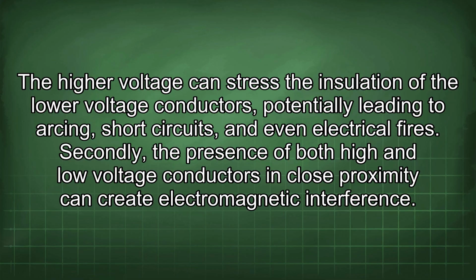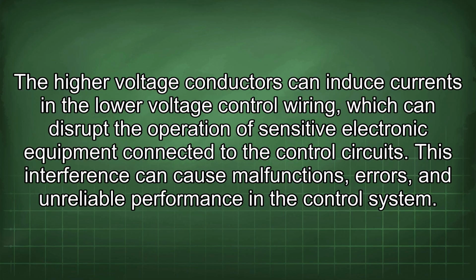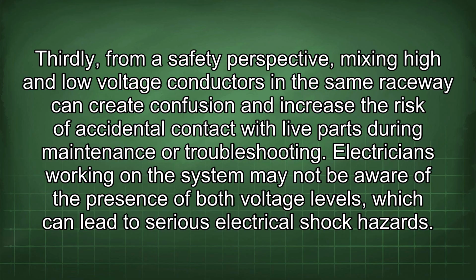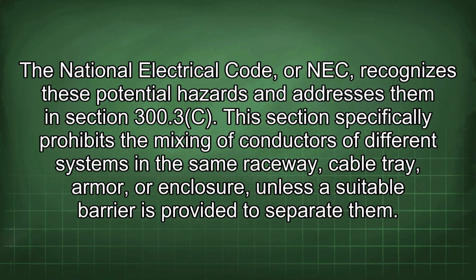electrical fires. Secondly, the presence of both high and low voltage conductors in close proximity can create electromagnetic interference. The higher voltage conductors can induce currents in the lower voltage control wiring, which can disrupt the operation of sensitive electronic equipment connected to the control circuits. This interference can cause malfunctions, errors, and unreliable performance in the control system. Thirdly, from a safety perspective, mixing high and low voltage conductors in the same raceway can create confusion and increase the risk of accidental contact with live parts during maintenance or troubleshooting. Electricians working on the system may not be aware of the presence of both voltage levels, which can lead to serious electrical shock hazards. The National Electrical Code, or NEC, recognizes these potential hazards and addresses them in Section 300.3(C).